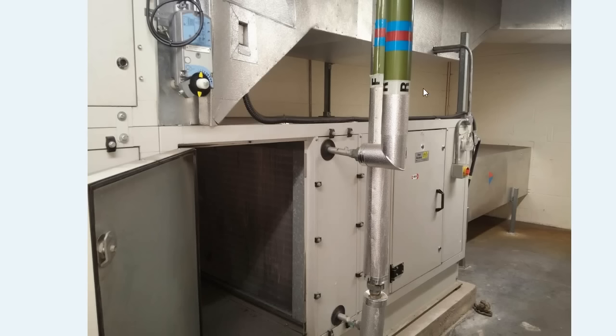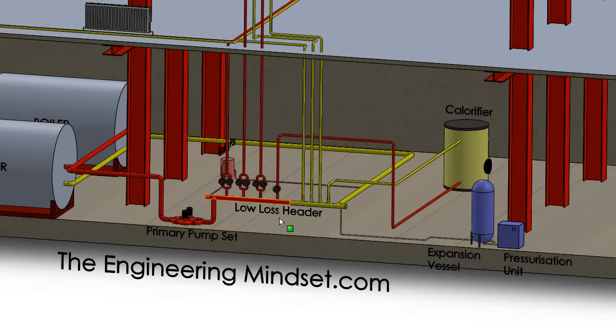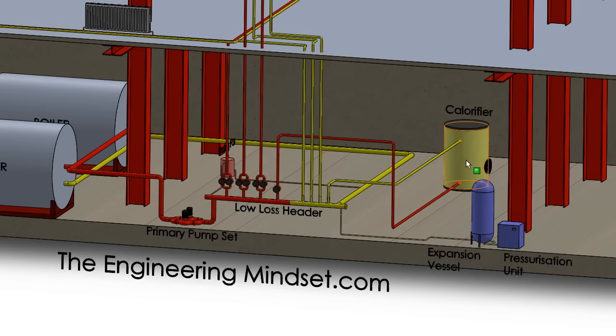I'll just show you an example of the heating coil on an AHU. So here we've got the flow water coming in from that secondary system, entering into this heating coil where it gives up its heat to the air. That heated air then goes off and is provided into the office space. Meanwhile that heating water returns at a cooler temperature and heads back to the boiler. And the final secondary circuit is this one here — it's going off and feeding into a calorifier.